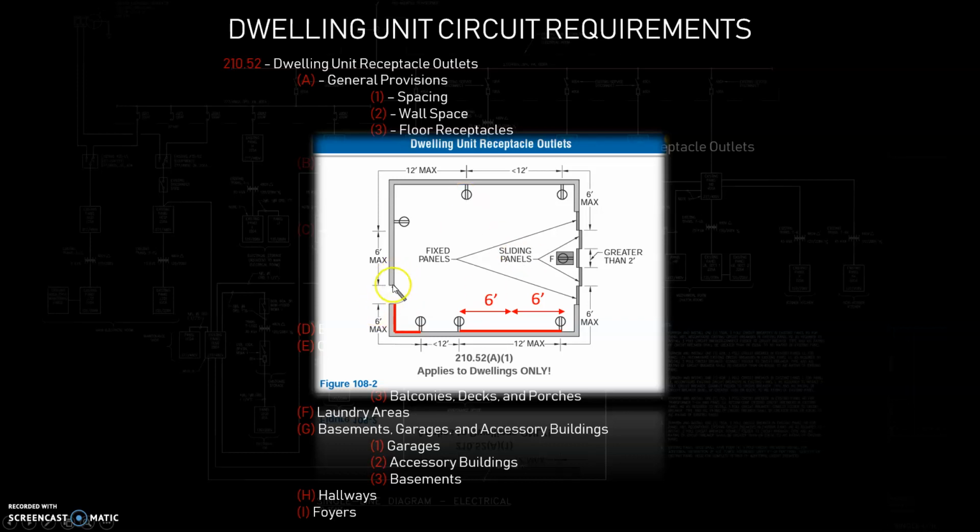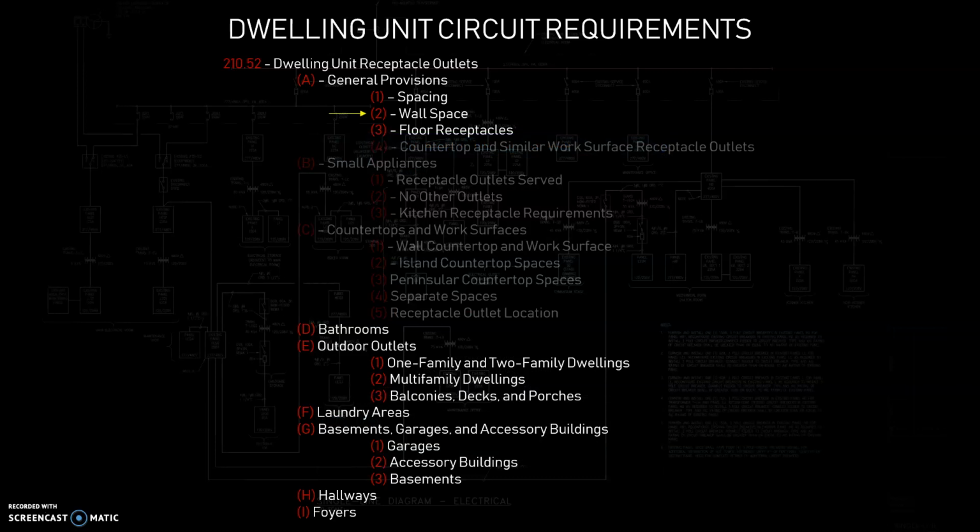So again, we have sort of this 6 foot space from the wall break or the start of a wall to the first receptacle. Then we have 12 foot to the next receptacle, right? That's a big one. You're going to see that quite a lot. Remember that one.